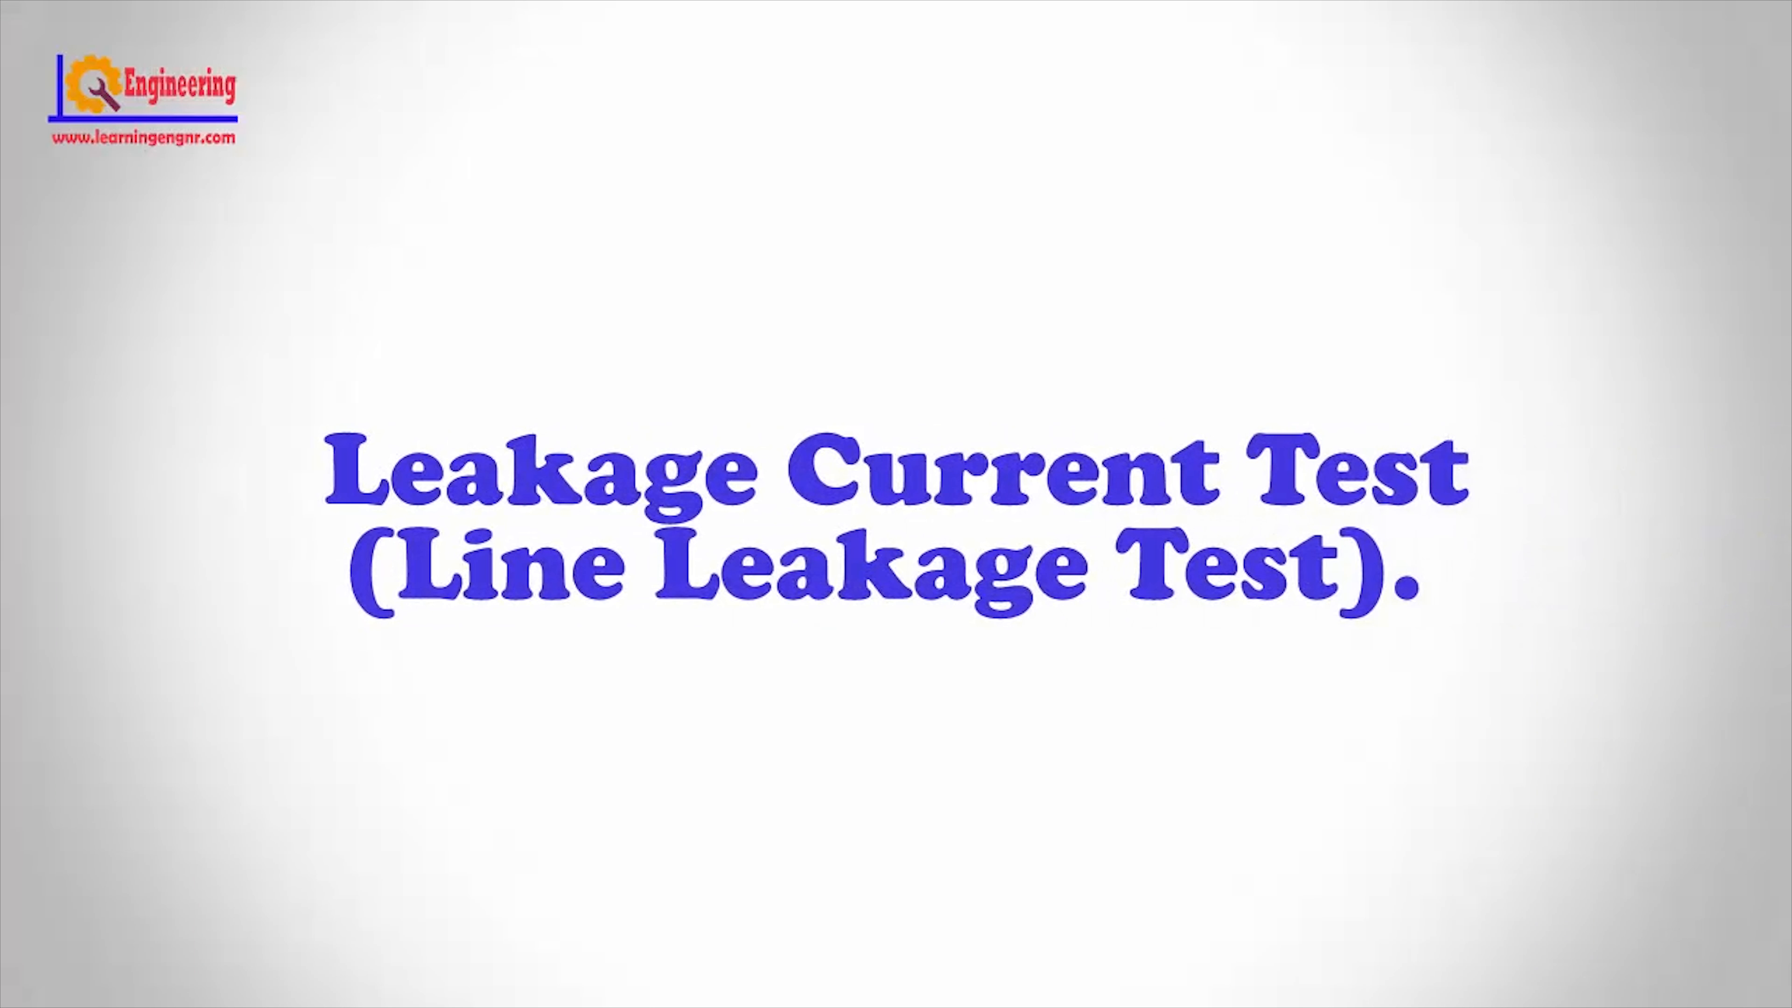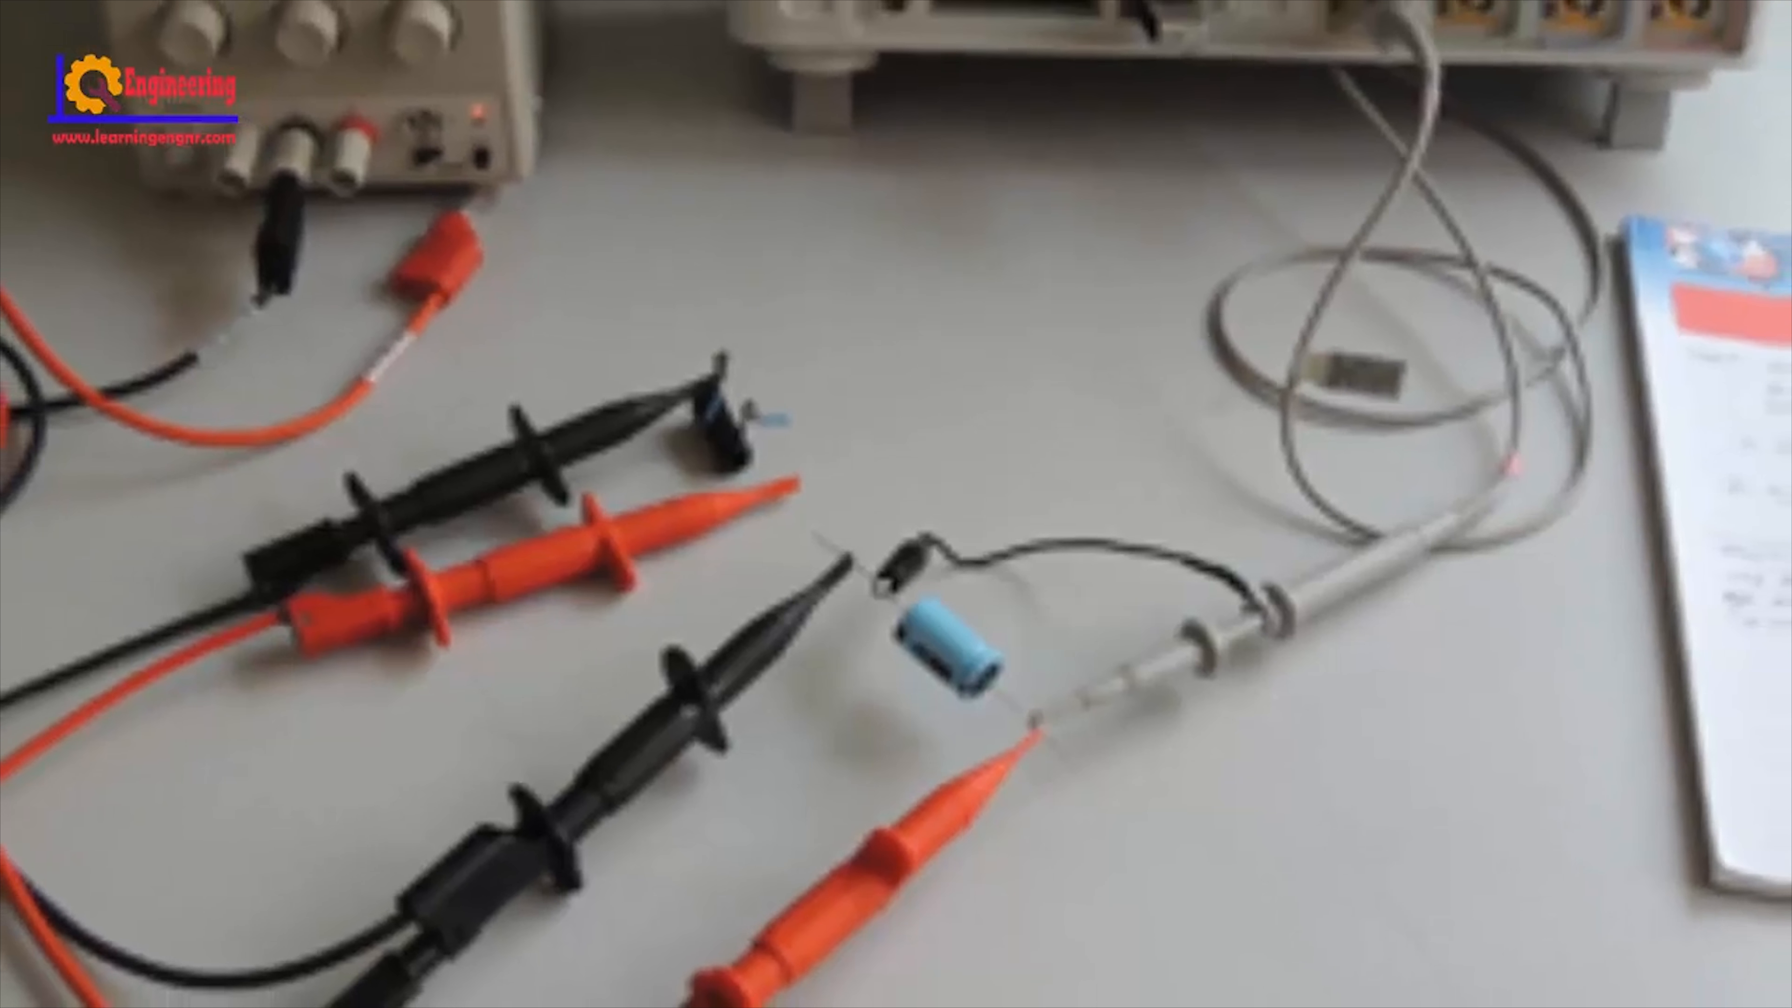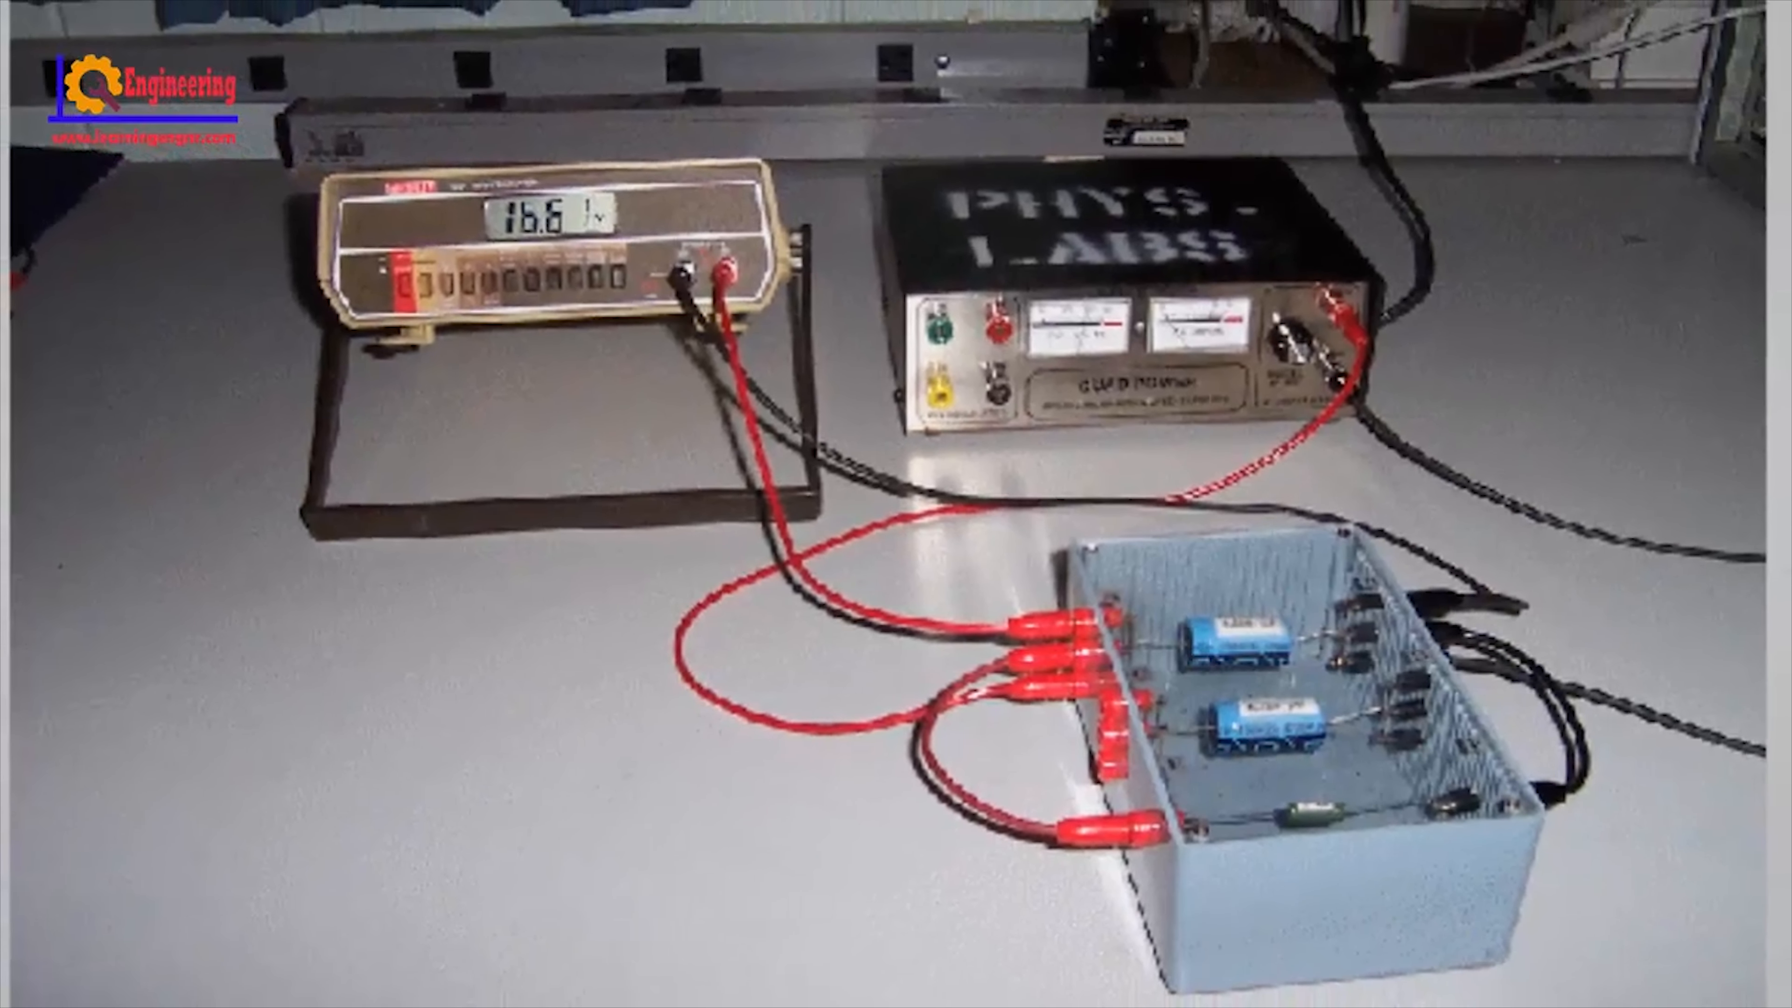Leakage Current Test Line Leakage Test. This test is to measure the undesirable leakage current that flows through or across the surface of the insulation or the dielectric of a capacitor. This test is generally carried out at 100% to 110% of the rated input voltage of the product under test.